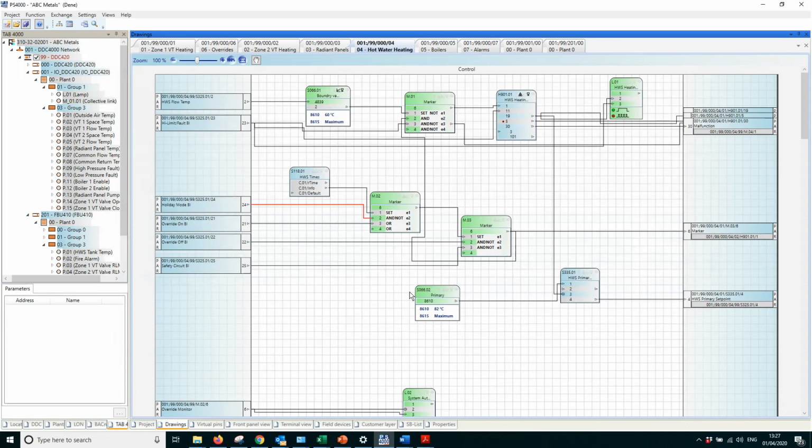Right, another nice search feature is by setting up the log data. Now in the DDC420 which we're programming, we have a data record size limit of 2,500 parameters, or 2,500 records. If we were logging 10 points, that means that each point could have a bucket of 250 parameters. So it's a good check to see how many trend curves you've got configured, and then you can allocate the bucket size accordingly depending upon what type of pin it is.